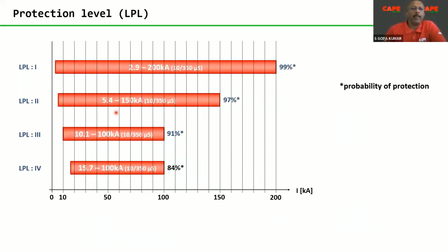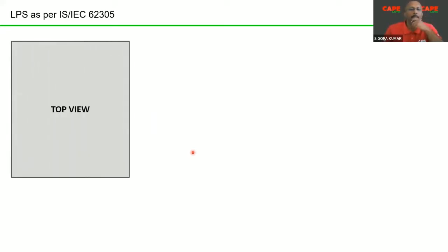Level 1 to 4, depending upon the current. For example, level 1, 2.9 to 200 kiloampere. Level 4, 15.7 to 100 kiloampere. So 4 levels. The purpose of finding out the level is to find out whether the economics, the cost which you are spending, is worth it or not. That is a simple method. Now, how does lightning protection look in a typical building? I'm just showing you. Some of you probably already know this particular picture because this typical picture I always refer to.